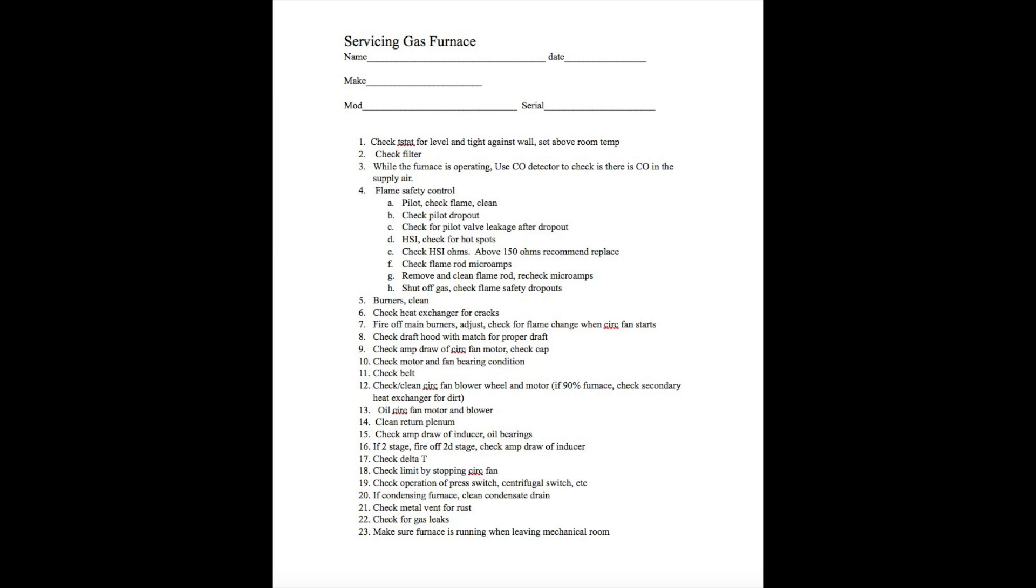If it's a condensing furnace, as in a 90% furnace, you're going to have to clean the condensate drain. That's another good one for your vacuum cleaner. You can suck out the P-trap and so on with a shop vac. You've got to be kind of careful and not get too rambunctious with putting a lot of vacuum on it, but just enough to pull any water out of the P-trap. One little note here, you may have to refill that P-trap before the unit will run normally.